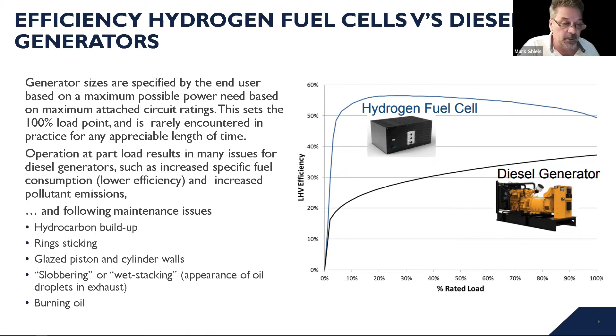Now, if you look at the graph on the right, it illustrates the differences in efficiency between a diesel generator and a fuel cell. Fuel cell efficiency is different. It's a chemical reaction, and as such, its efficiency can increase as the load is decreased. So if I go from 100% down to 50%, my efficiency will effectively still be the same. Diesel generators, by contrast, the diesel efficiency usually decreases from 100% down through all parts of the load. And if you size DGs for peak demand but run them at part load, you end up having low efficiency, more emissions, and you burn more fuel to provide the same amount of power.